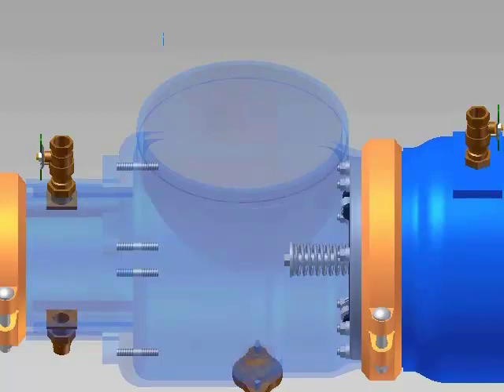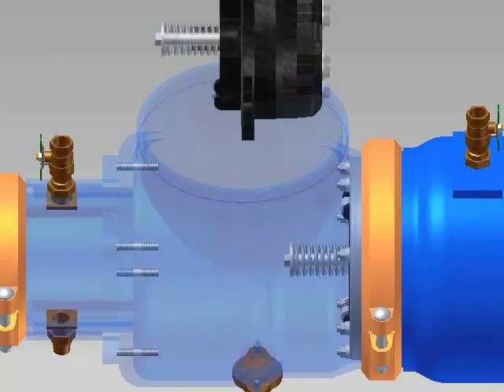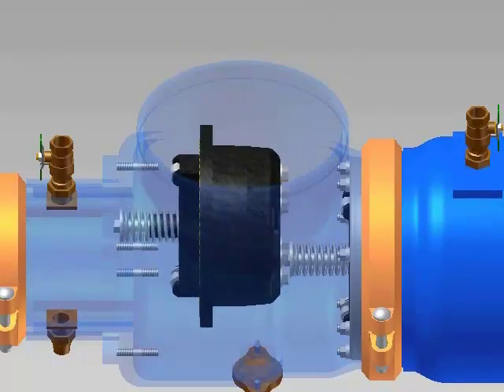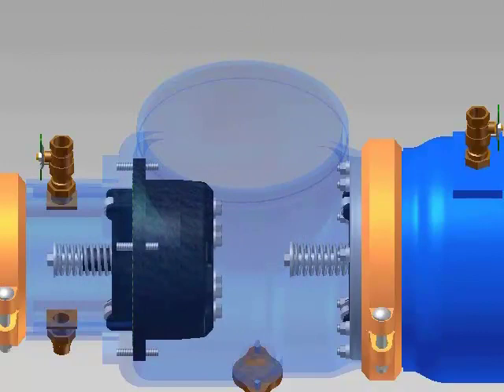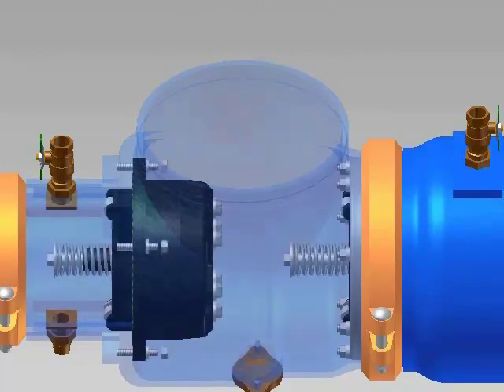When placing the check assemblies back onto the studs in the body, you want to make sure the O-ring stays in its groove. Place number 1 check assembly onto its studs in the body. Place the four washers and nuts on the studs and tighten the nuts evenly.